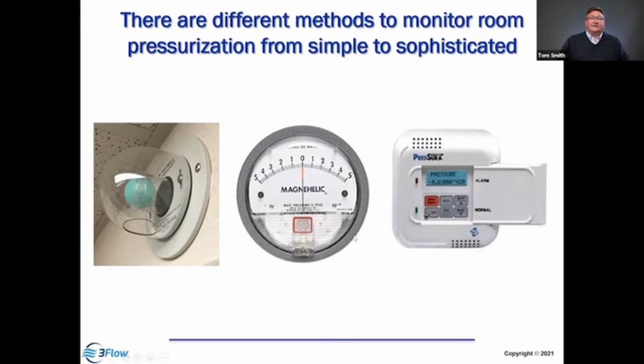The magnehelic gauge is another very inexpensive gauge that you can use to measure the differential pressure. It's a sight type of gauge. And then you have your electronic gauges that are based on pressurization. This gauge needs to be calibrated and then reflect the actual pressure. And now you can use that in the monitoring and maintenance of the systems.